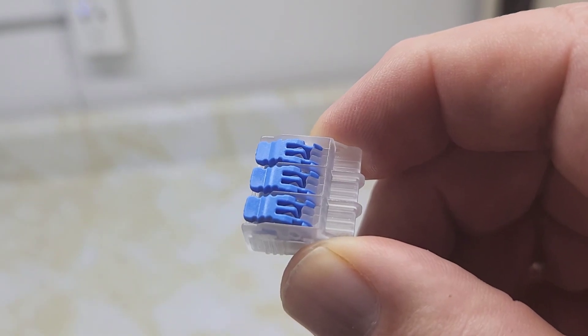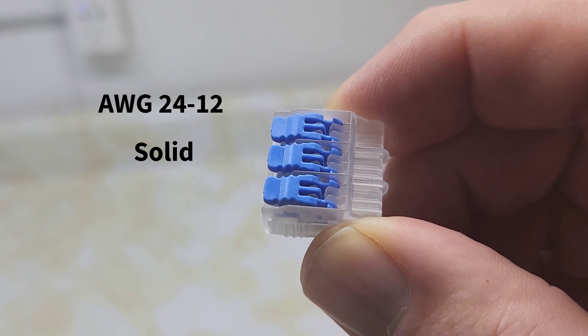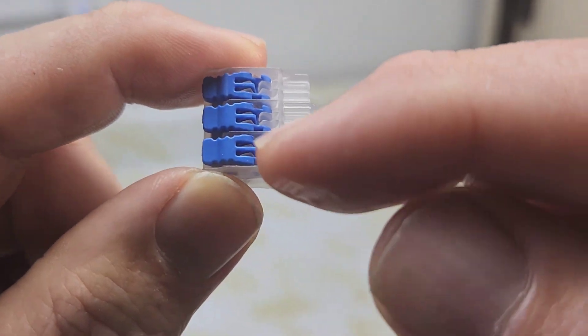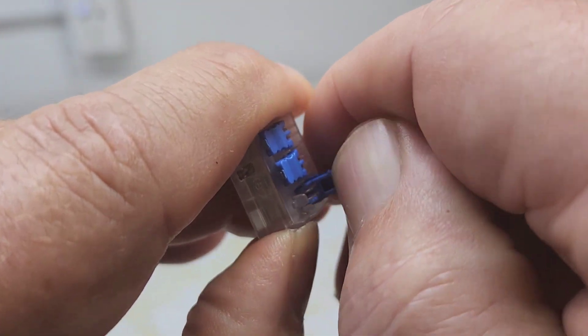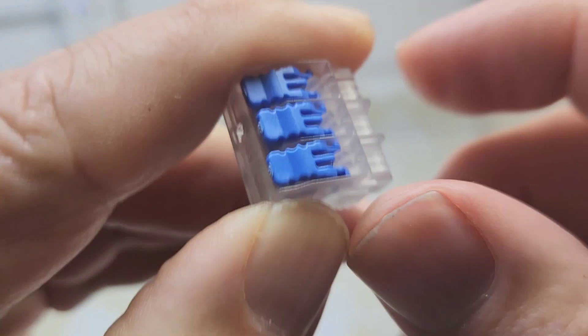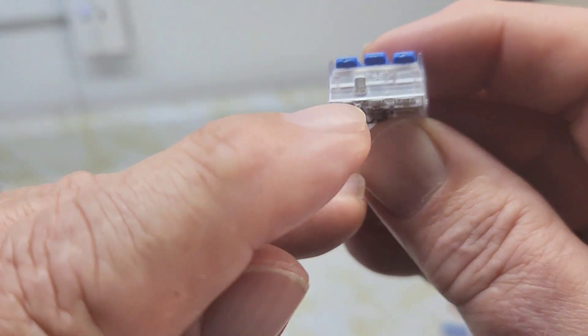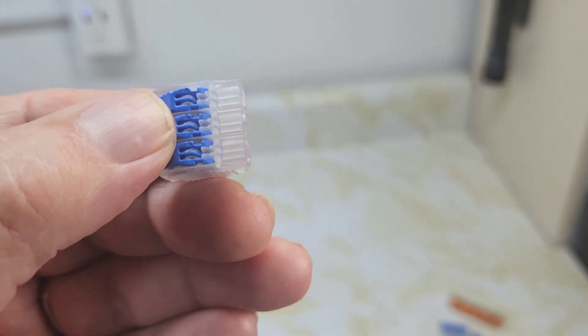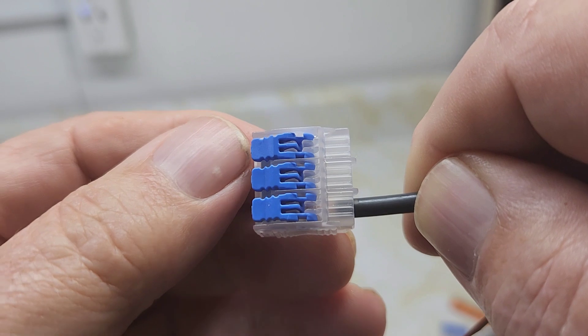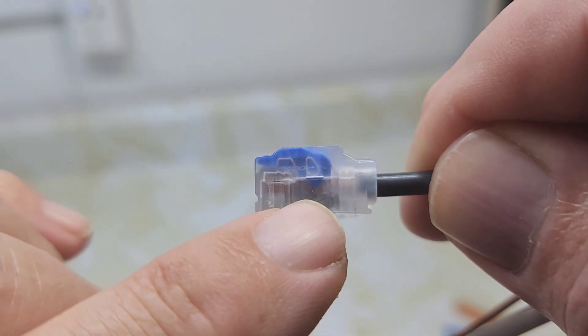I really like these Ideal lever wire connectors. Comes in two, three, and five port. It can accommodate from AWG 24 to 12 solid wire, AWG 24 to 12 stranded wire. I like the way the wire comes in on this side and the levers on the opposite side. You look at the lever here - it actually has a small little notch in here and a hole up here. So when you press it down, it snaps in place. Less chance of when you're putting all your wires in the electrical box this coming up on you. It has a test port here as well as here. When you're using solid wire - this is number 12 solid wire - you just have to press it in here. You don't have to lift up the lever. The only time you have to lift up the levers is when you're using stranded wire. You can see the copper wire in here, not as clear as the Wago ones, and slightly thicker than the Wago ones.